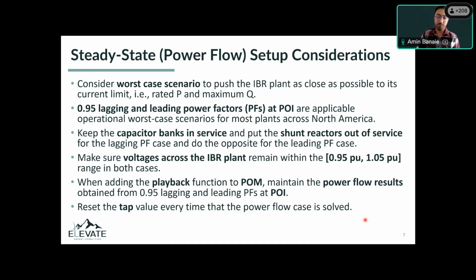And if an IBR site is going to operate at Q max, then the first option is to use the cap banks in the plant and not use the inverters to generate Q and get closer to their current limits. And you want to put the shunt reactors out of service and do the opposite for the leading case. And this is going to make your case realistic as well.